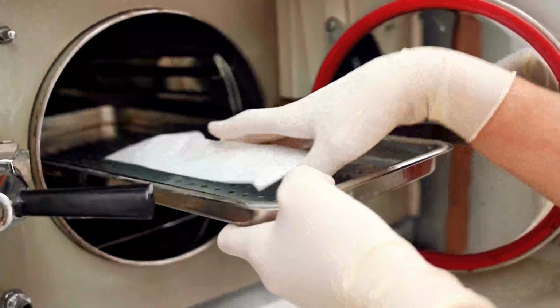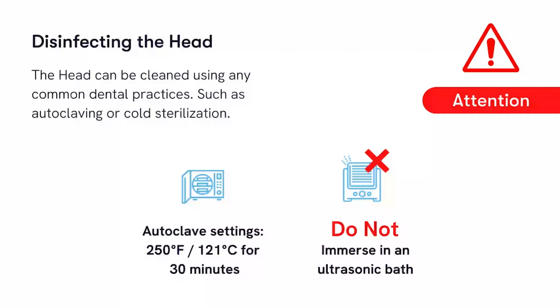The head can be cleaned using any common dental practices, such as autoclaving or cold sterilization. Autoclave at 250 degrees Fahrenheit or 121 degrees Celsius for 30 minutes. Be sure to never immerse in an ultrasonic bath.